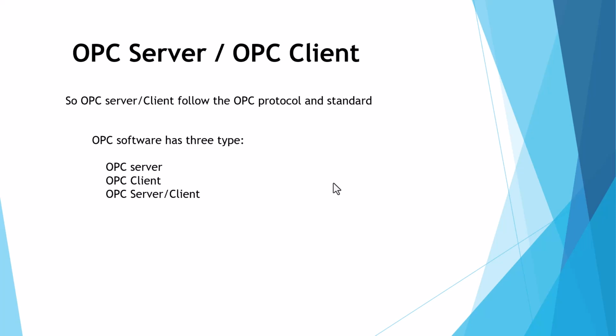OPC has a server and an OPC client. The OPC server and client follow the OPC protocol and standard. OPC server is OPC server software, and OPC client is OPC client software, independent or from some OPC server and client company. So maybe a company develops the OPC server and OPC client independently. But if you want to use OPC, you have to have two pieces of software, server and client, or server and client combined together as one piece of software.